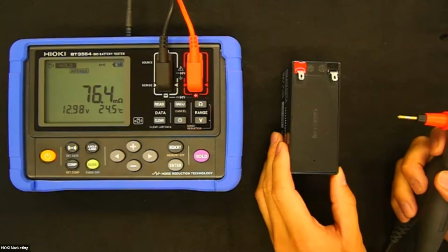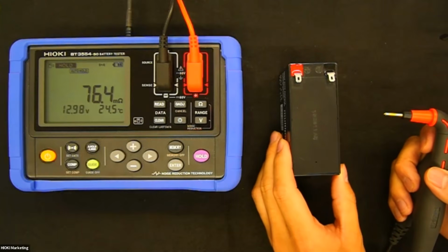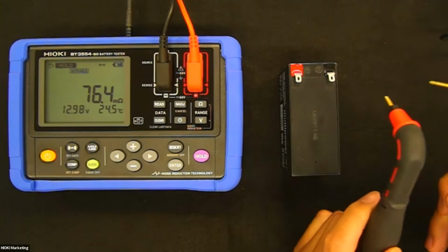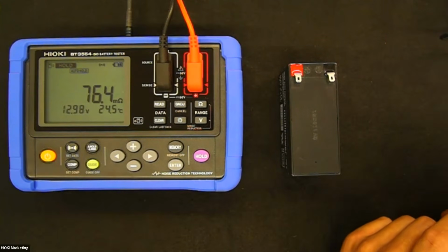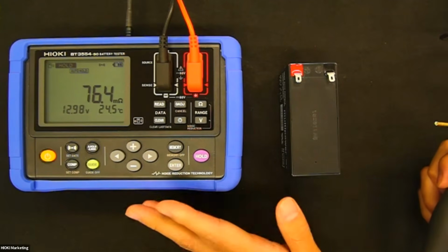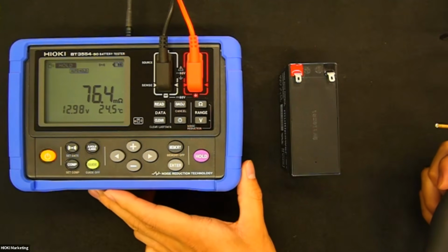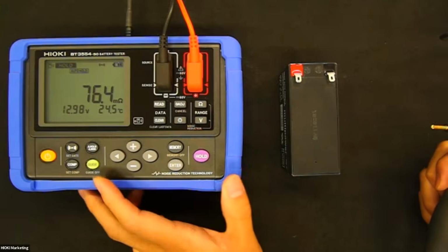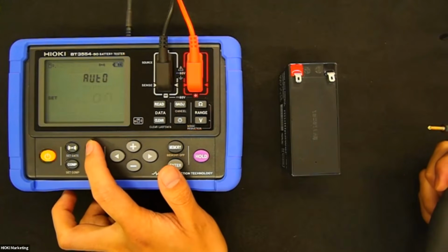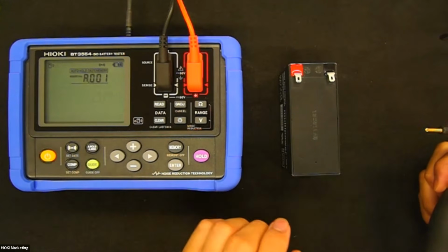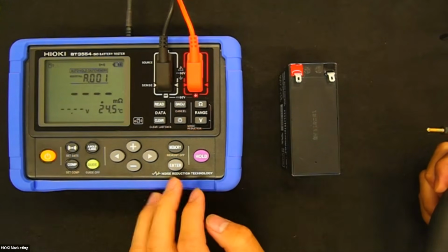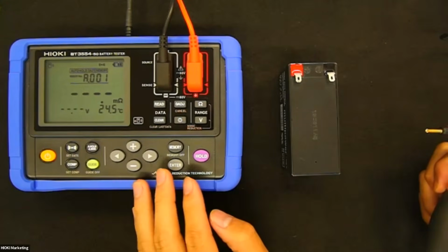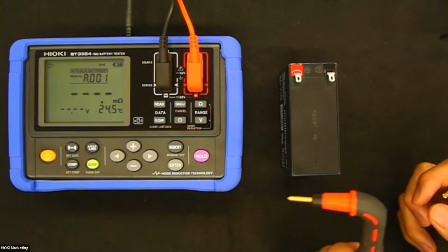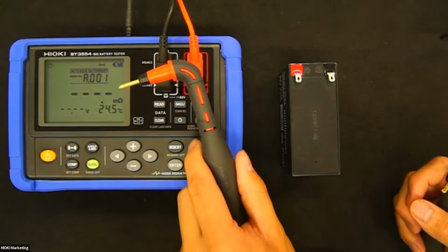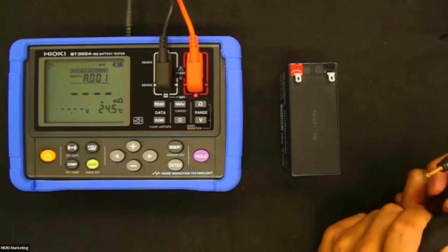In actual UPS maintenance situations, you have to test multiple battery cells. In that case, the auto memory function is very useful. It can store the data in the internal memory of the device automatically, and now you can see the memory number on the top of the display.